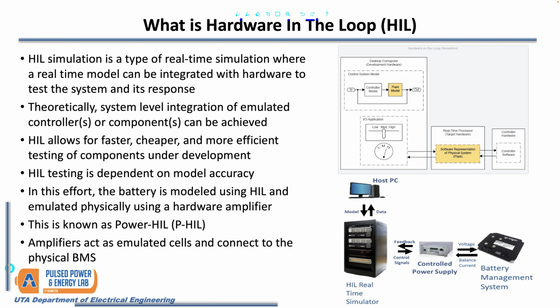So I mentioned hardware-in-the-loop. What is it? Hardware-in-the-loop simulation allows us to deploy a model that is in software to the external world. This is important because now a device might look at this output and think it's a real device. Simply put, we take that model of a battery and hook it up to a power supply, and as far as the battery management system is concerned, it sees an actual battery. This lets us fake the BMS into thinking it's hooked up to a battery, giving us a situation that's faster to test and safer, because the hardware-in-the-loop simulation can be turned off with no chance of thermal runaway, and since it's a power supply, its output is much more limited.